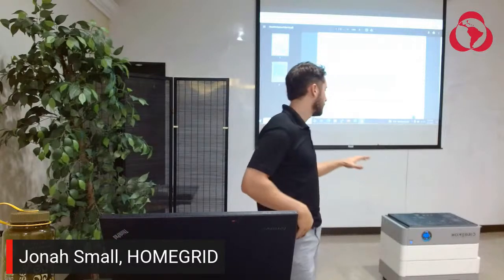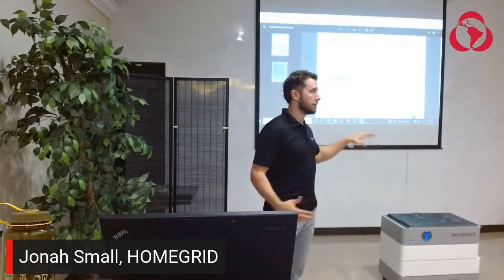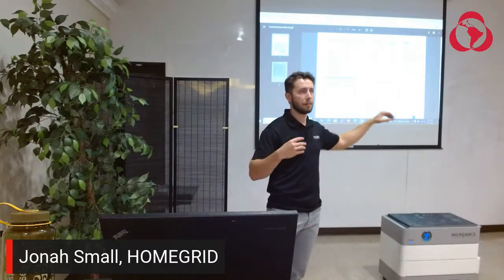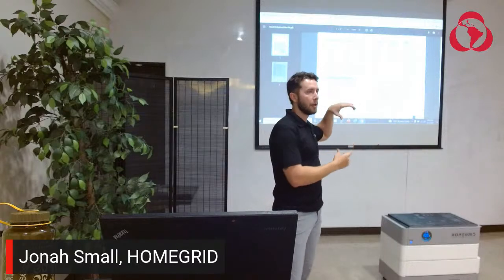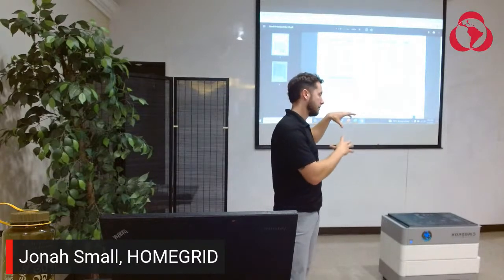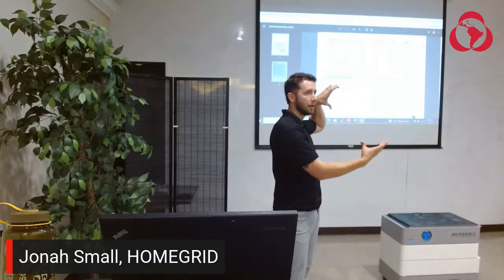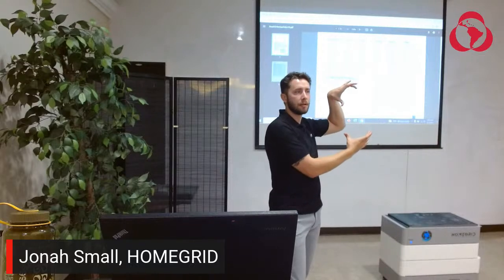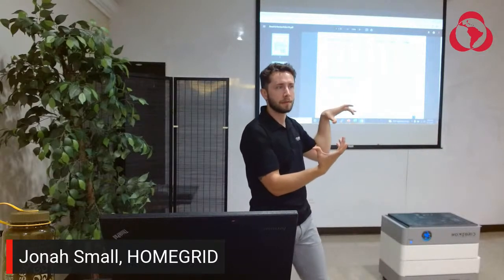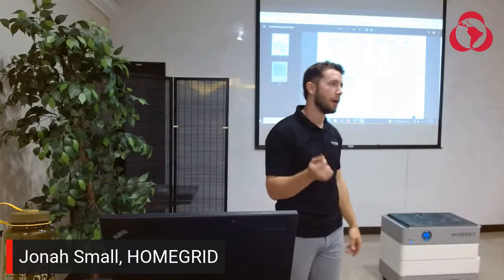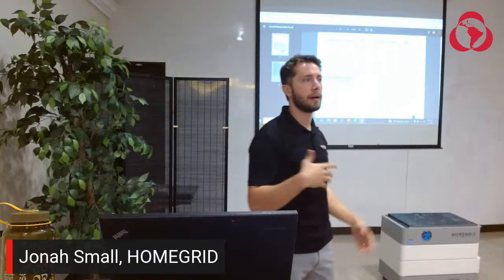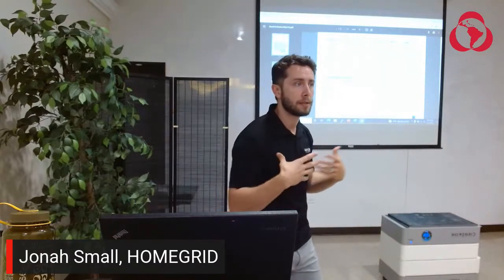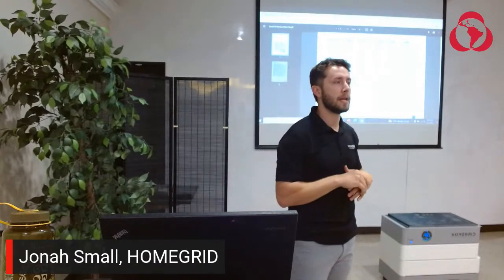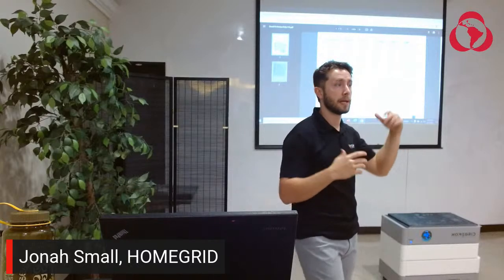I just want to be really clear that the charging from the generator comes through the solar converter, so the solar gets limited to what the solar can handle. It depends on which model you use from them, but they can auto-start the generator to charge the battery, and we capture that full 5 kilowatts or 10 kilowatts. It comes down to which model solar you're using as to how big you can go.